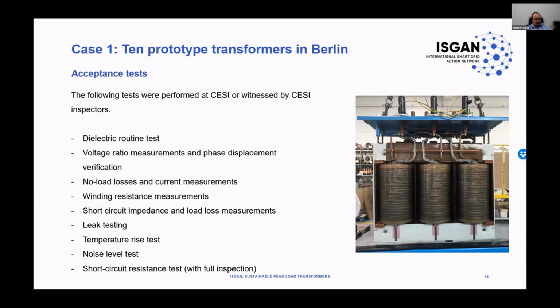We performed a noise level test. One bigger advantage of this type of transformer is the reduced noise compared with the standard transformer, due to the reduced no-load losses that it generates. And for sure, we also performed a short circuit resistance test with full inspection after the test. Obviously, all these tests were performed by the manufacturer in an external laboratory, were successful, and the transformers were accepted by the customer.